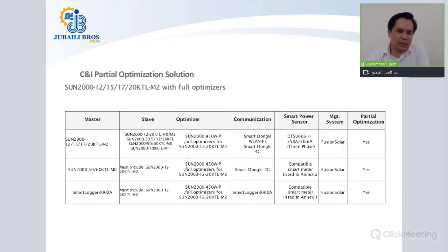So the second scenario is a 50 and 60 kTL inverter type, and so a slave inverter must include 12 to 20 kilowatt, because the partial optimization will only happen with a 12 to 20 kilowatt inverter, since 50 and 60 still don't support the optimizer. With a Smart Logger 3000A, the third scenario is a master device, and the slave inverters must include at least one 12 to 20 kilowatt inverter size to do the partial optimization. The power optimizer itself is the 450 watt size from Huawei.